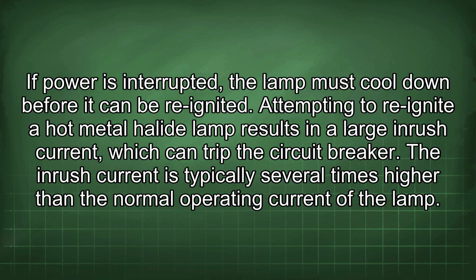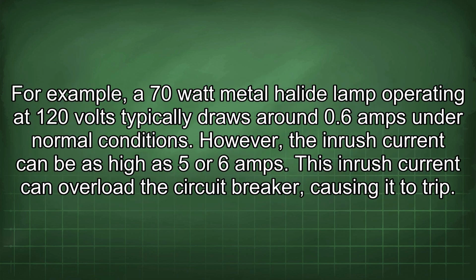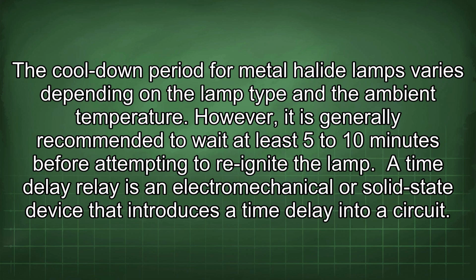The inrush current is typically several times higher than the normal operating current of the lamp. For example, a 70-watt metal halide lamp operating at 120 volts typically draws around 0.6 amps under normal conditions. However, the inrush current can be as high as 5 or 6 amps. This inrush current can overload the circuit breaker, causing it to trip. The cool-down period for metal halide lamps varies depending on the lamp type and the ambient temperature. However, it is generally recommended to wait at least 5 to 10 minutes before attempting to reignite the lamp.